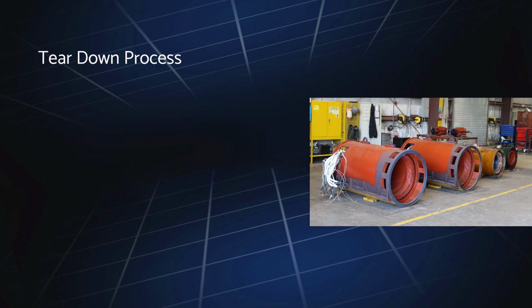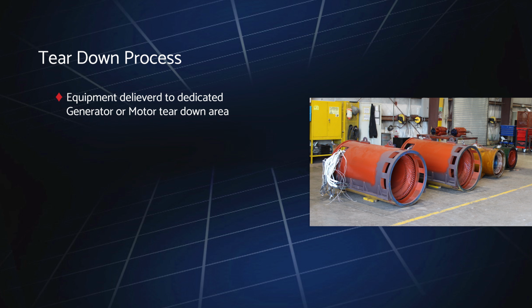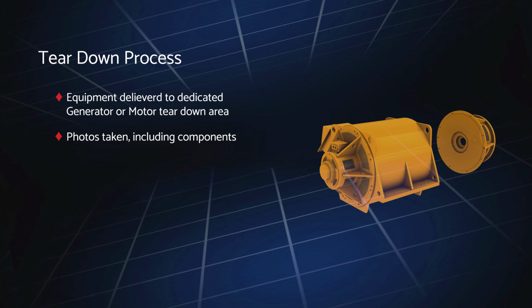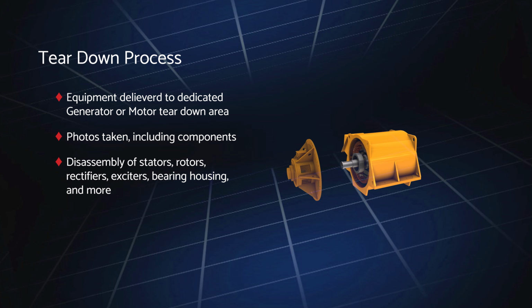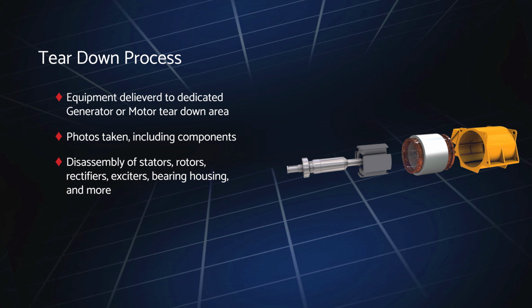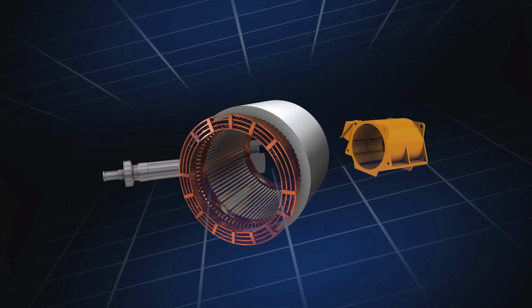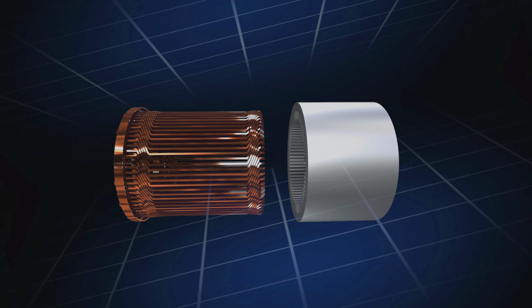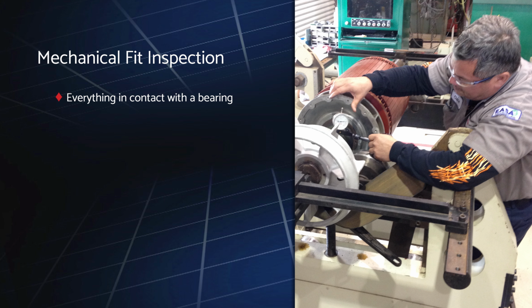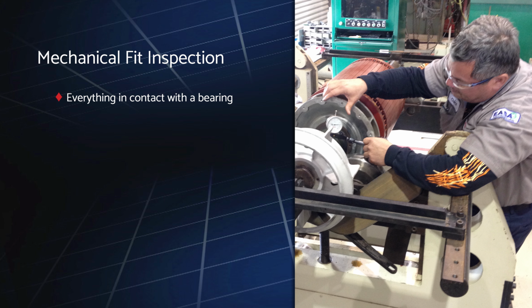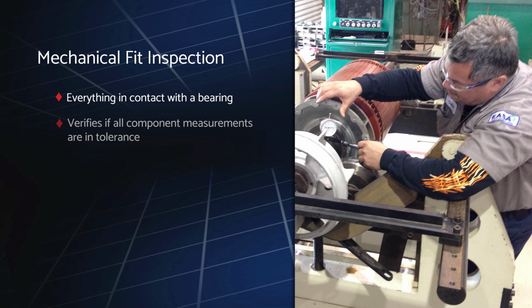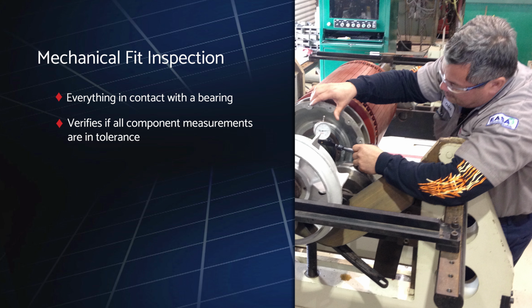Once a piece of equipment is delivered, it is brought to our dedicated generator or motor teardown area, where it and all of its key components are photographed and disassembled, including stators, rotors, rectifiers, exciters, bearing housing, end bells, and more. We then do a mechanical fit inspection of everything that comes in contact with the bearing to verify that all component measurements are in tolerance.